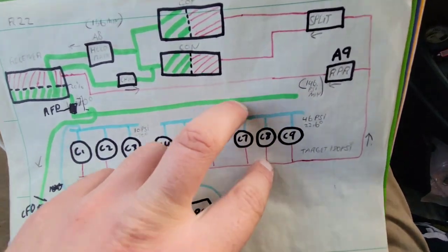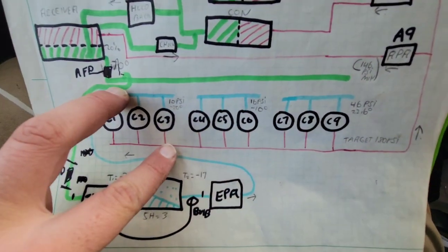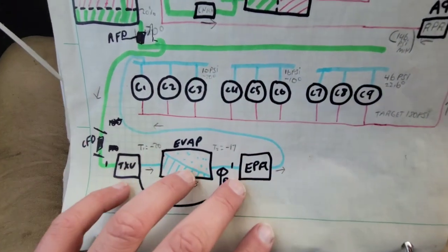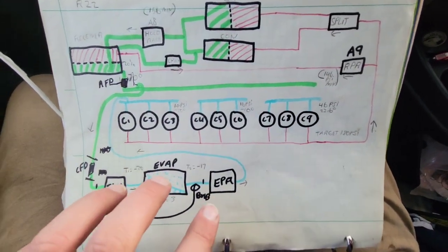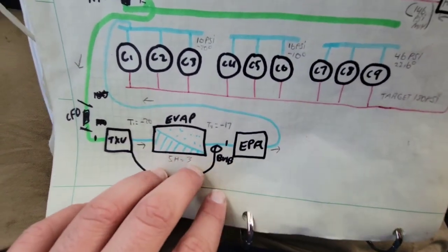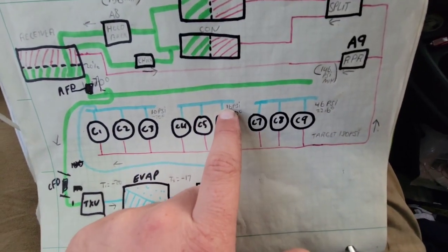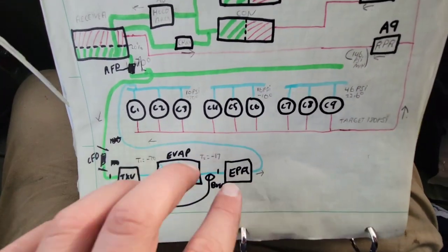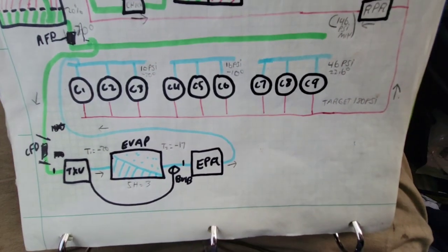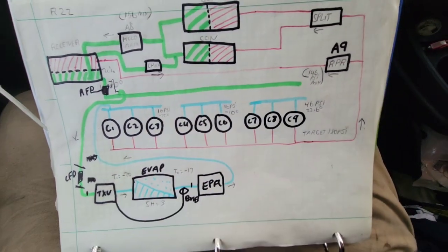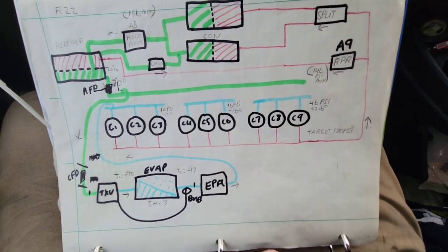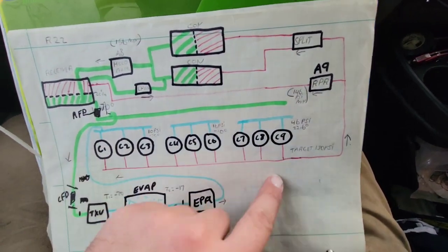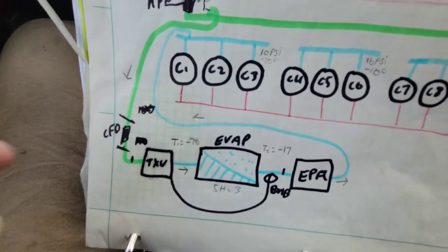Which is your pressures, your discharge and your suction pressure. Now, if your rack is not working properly, you can't troubleshoot your case. Why? Because you're going to get weird stuff happening down here. For instance, if your suction pressure is not right at your rack, your suction pressure is not going to be right at your case. And if you focus on the case first, you might think it's an EPR, when in reality it's because your compressors are off on safety. Or if you're not flowing refrigerant properly, you don't have high enough head pressure or something, you might think it's the filter dryer.